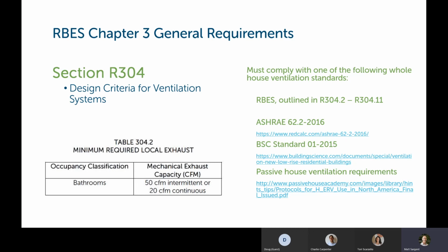Or you can, you must comply with, for whole house ventilation, you must comply with either the RBES ventilation standard, which is outlined in 304.2 through 304.11, or the ASHRAE standard 62.2 2016, and there is a link there to a calculator that can calculate that value for you.